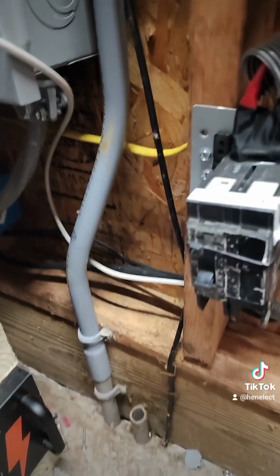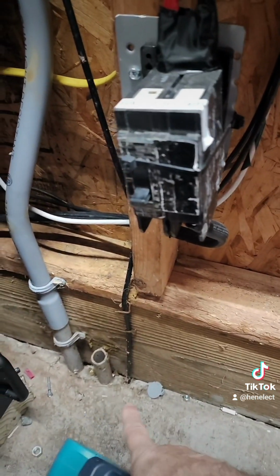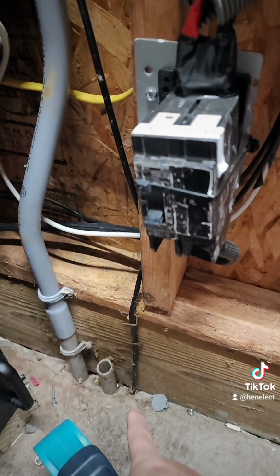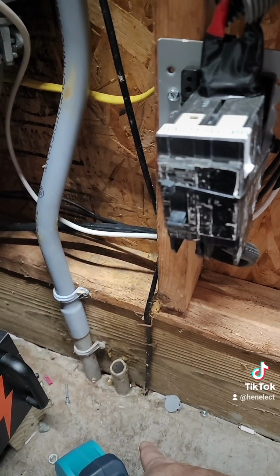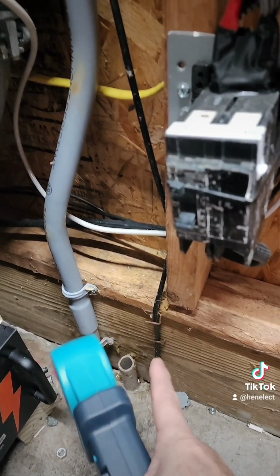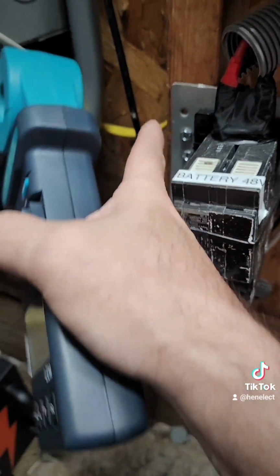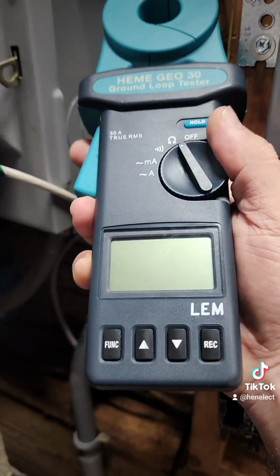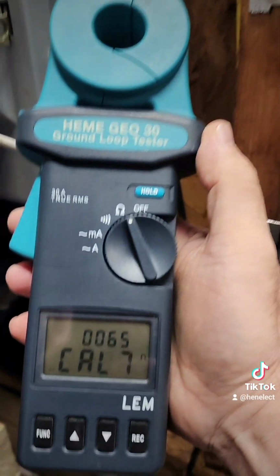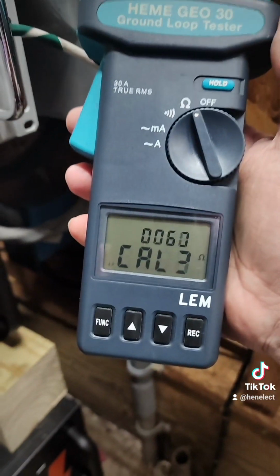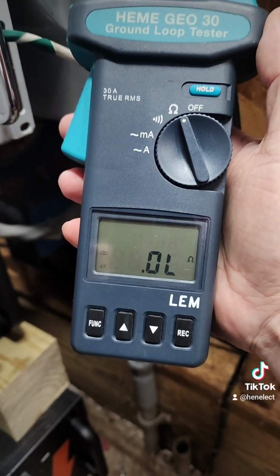Okay, let's go test this out on my ground here at the shop. Okay, I'm here where my incoming power comes into my shop. This is my ground wire. I built this a while ago, so the ground wire is actually embedded in concrete below us. So here's my ground wire. I just pulled the staple off to give me some room to bite in. So what I'm going to do is to test it, I'm going to turn it on. I can hear it beeping. It's going to calibrate. Once it gets to overload, now I'm ready.